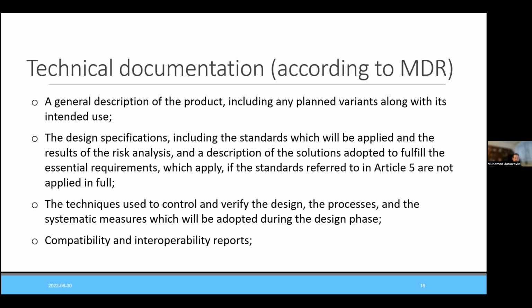One of the main non-functional components of the medical device is the technical documentation. The medical device regulation outlines the content and requirements for preparation of the technical documentation. It contains a general description of the product, including any planned variants along with the intended use, the design specification, including standards which will be applied, then a result of the risk assessment, description of solutions adopted to fulfill the essential requirements, standards referred to in some requirements of the MDR, then techniques used to control and verify the design, the processes, systematic measures which will be adopted during the design phases, compatibility, interoperability reports, and similar things.